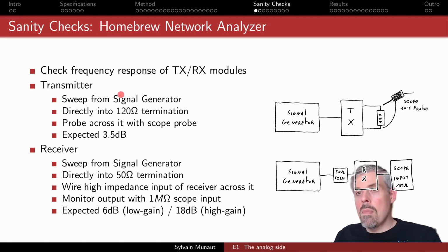So the test for the transmitter is simply take the signal from the signal generator, put it through the transmit module, terminate the output of the transmit module into a 120 ohm load, and look at it on a scope probe.